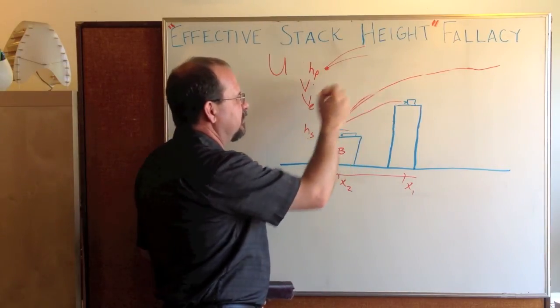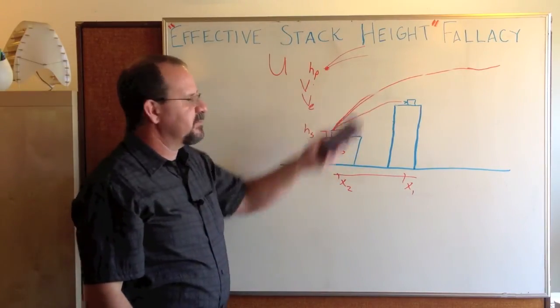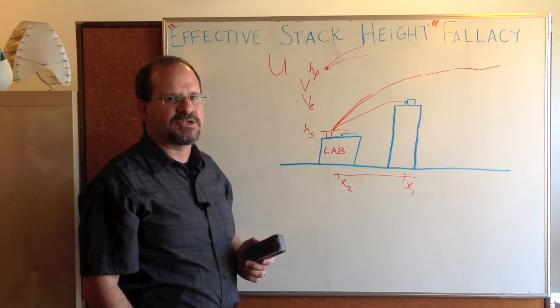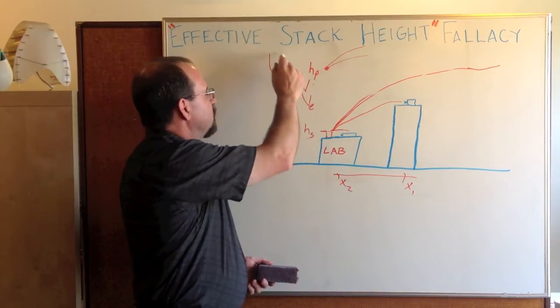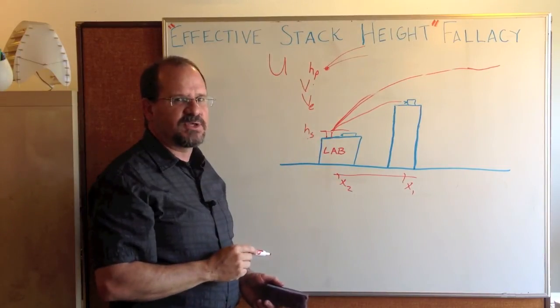For an intermediate wind speed, you'll end up with some intermediate plume rise. It could be a problem at a neighbor's air intake or a high air intake on your building. So you look at a whole range of wind speeds.